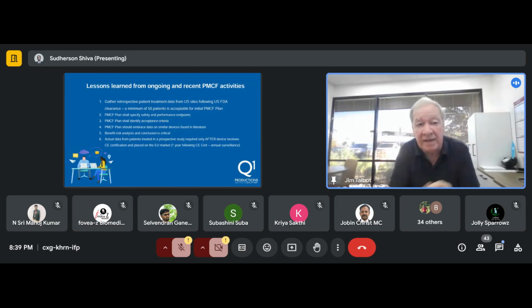And it's funny, these next few points I'm going to make seem very obvious, but you don't know how many companies submit their PMCF plan without defining safety and performance endpoints. It's probably the most important thing in your PMCF plan, but many notified bodies have indicated to me that that's the number one reason for rejection of PMCF plans and rejection of the technical documentation file, because adequate endpoints have not been established in the PMCF plan up front. With number 3, acceptance criteria. What is the minimum acceptance criteria you need to assure yourself that the test is intended?